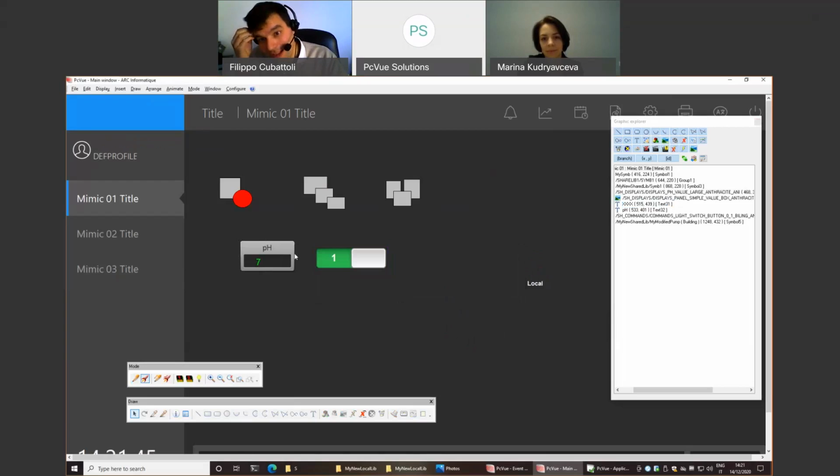So once you install PcVue on another PcVue station, you have to replace the lib folder provided by the default installation with your own lib folder. So it's better to avoid this and to clone this symbol in your own library, shared or local is not important, and use that symbol from your own library in order to avoid any corruption and any mistake.